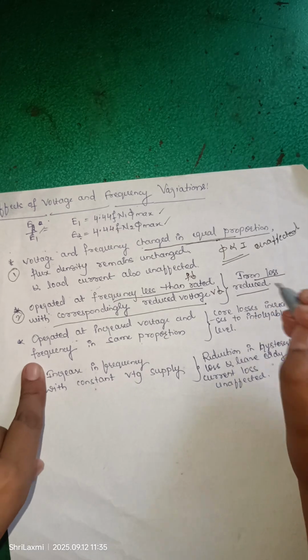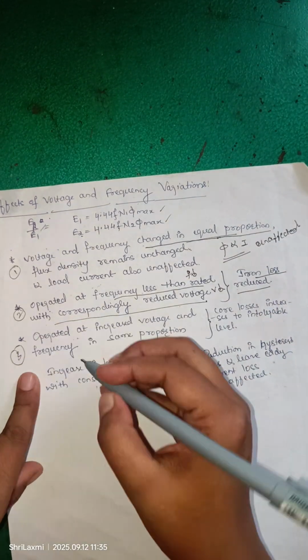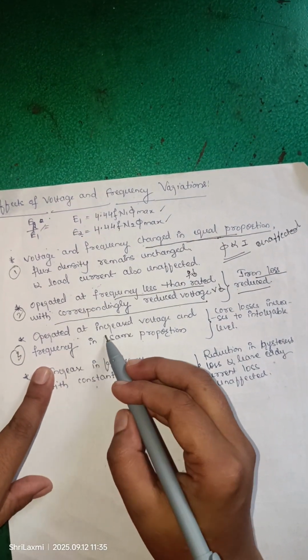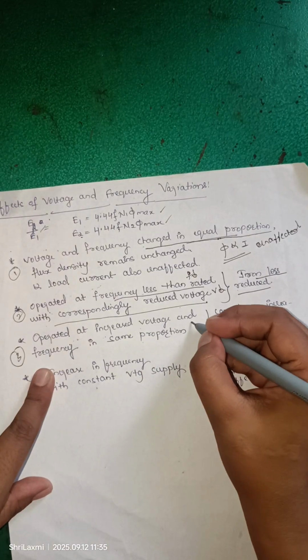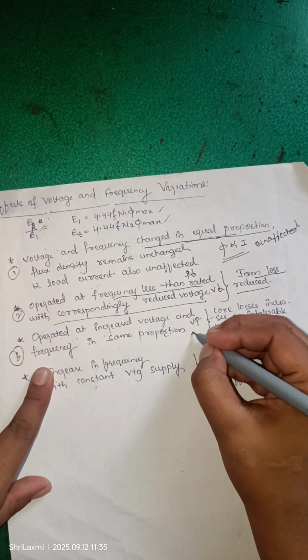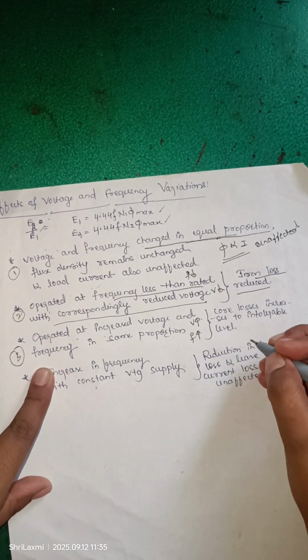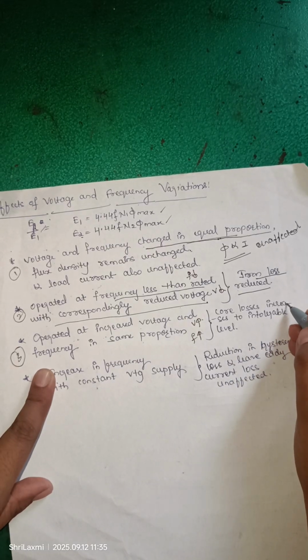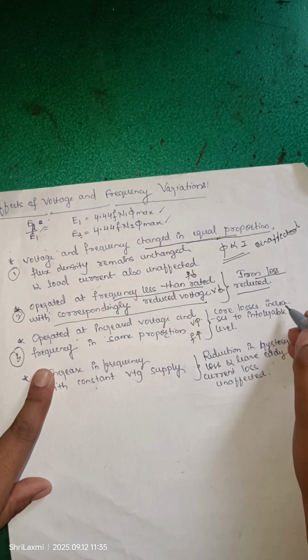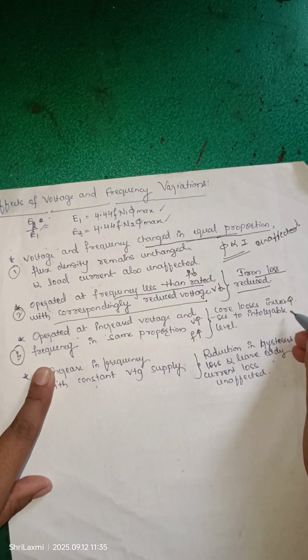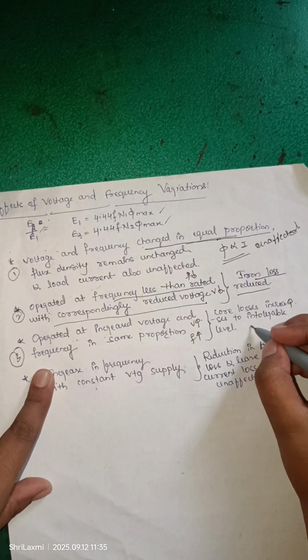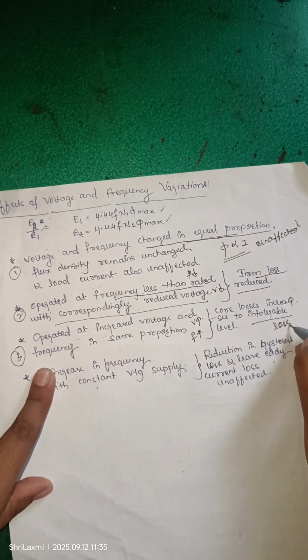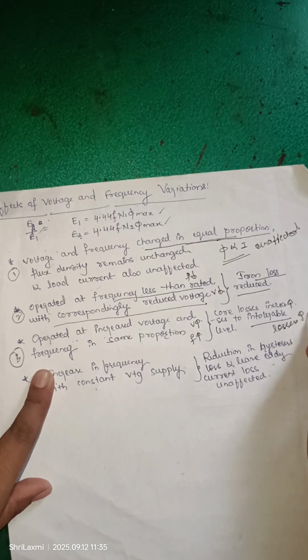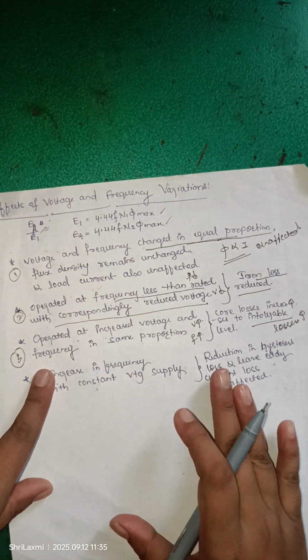In the third condition, if it is operated at increased voltage and frequency in the same proportion, core loss in the transformer increases to an intolerable level. So losses will increase more if you increase voltage and frequency.